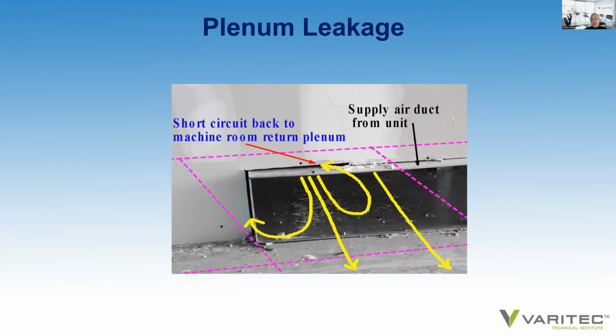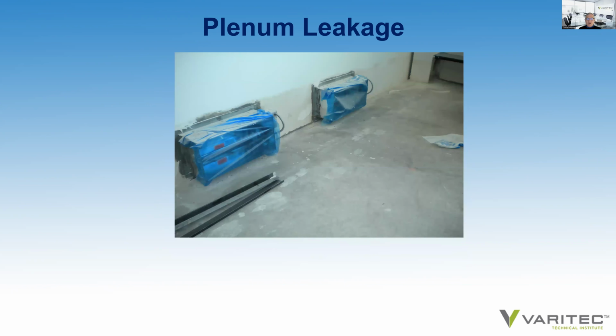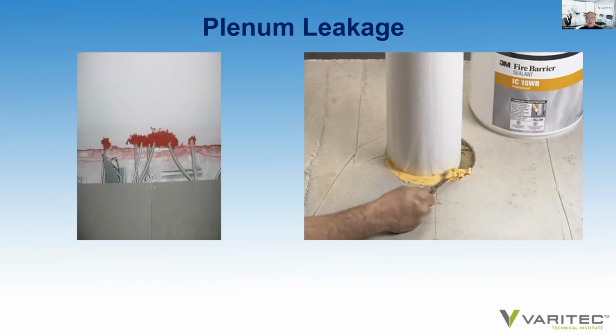Being part of a team to educate contractors on what to pay attention to, I've done before. We did that at the Madison Adaptive Reuse Project and educated the subcontractors that they're part of the mechanical team, that any penetration they make through the plenum has to be properly sealed, and we give them instructions on how to do so. So here are some visuals on how to properly seal penetrations through a floor to make sure there's zero leakage.